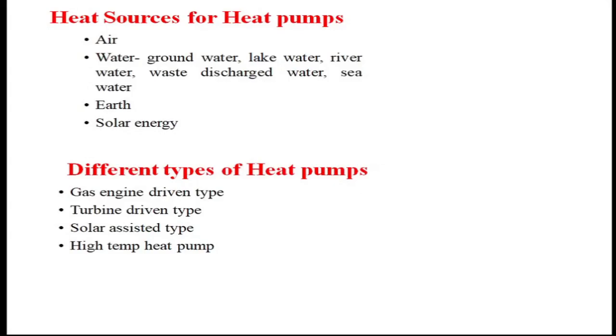What are the heat sources for heat pumps? In the case of heat pumps, we require a heat source which will be cooled and from which heat will be extracted and delivered to the condenser side. Heat sources can be air, water (groundwater, lake water, river water, wastewater, seawater), earth (soil), or solar energy. Types include gas engine driven, turbine driven, solar assisted, and high temperature heat pumps.